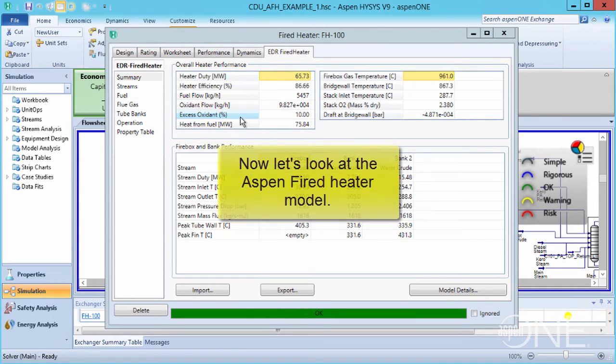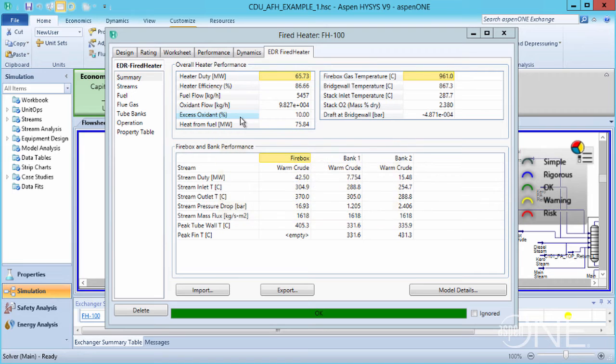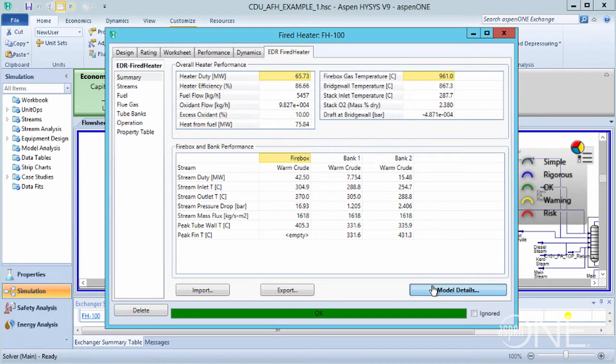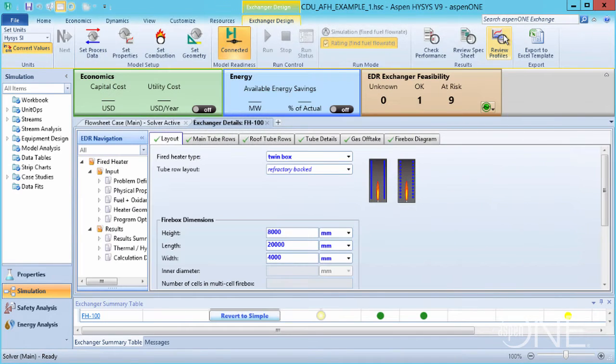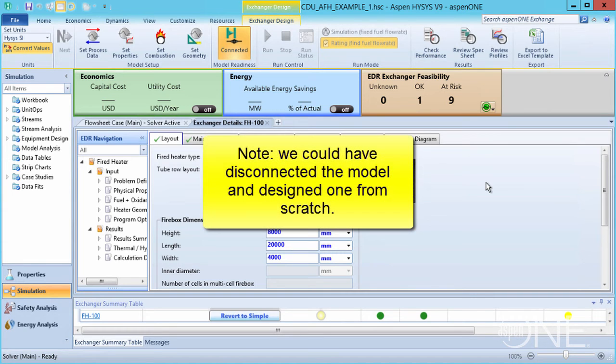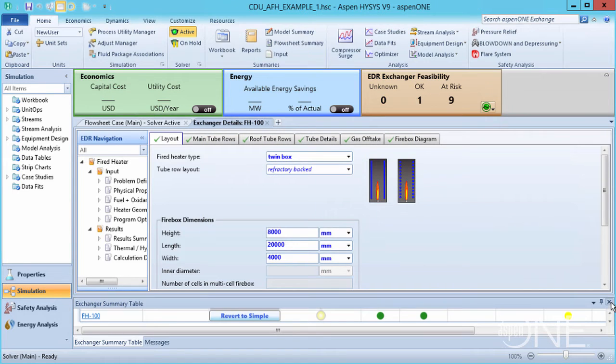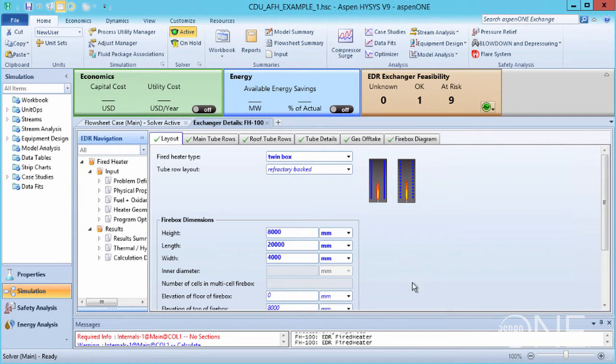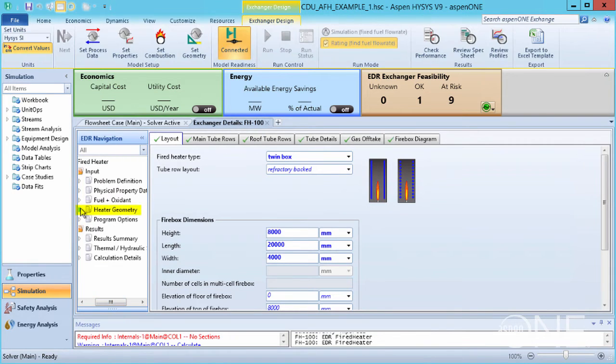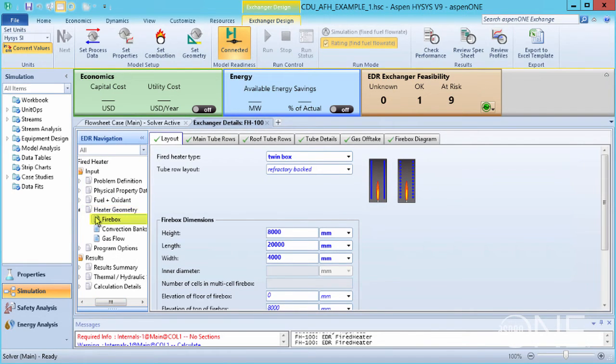Now let's look at the Aspen Fired Heater model to understand its geometry and other details. Click the Model Details button. This opens Aspen EDR within Aspen HYSYS. Note that instead of importing a previously prepared fired heater, we could have disconnected the model and designed one from scratch. Go to Input, Heater Geometry, Firebox, and you can see the furnace construction has twin boxes. These are 8 meters high, 20 meters long, and 4 meters wide.